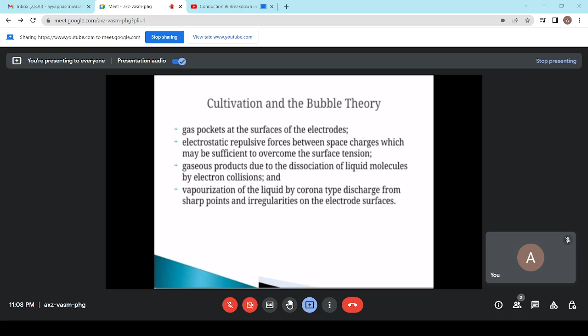Once a bubble is formed, it will be elongated in the direction of the electric field under the influence of electrostatic force. The volume of the bubble remains constant during elongation, and breakdown occurs when the voltage drop along the length of the bubble becomes equal to the minimum value on the Paschen's curve for the gas in the bubble. This breakdown field is given by E0 = 1 / (epsilon 1 minus epsilon 2) times [2 pi sigma (2 epsilon 1 plus epsilon 2) / r] raised to 1/2 times [pi/4 square root of Vb / (2r E0) minus 1] raised to 1/2.